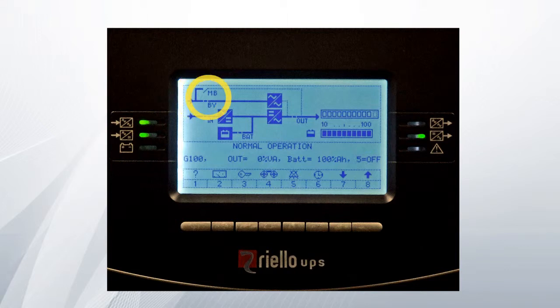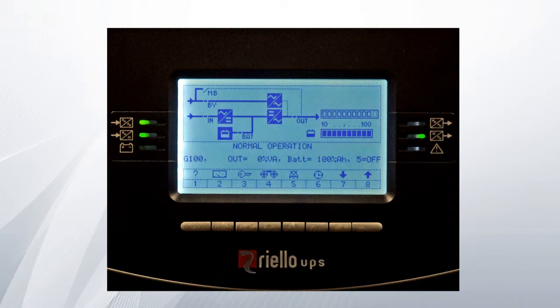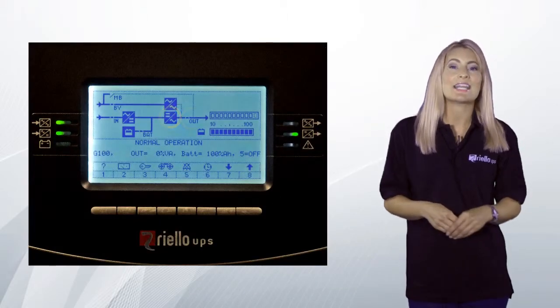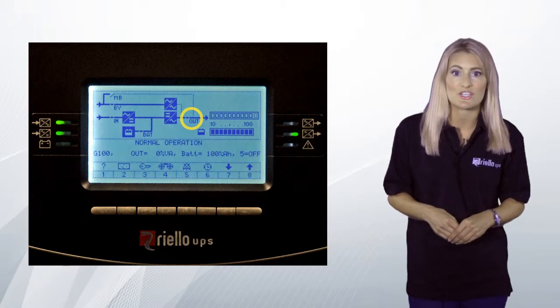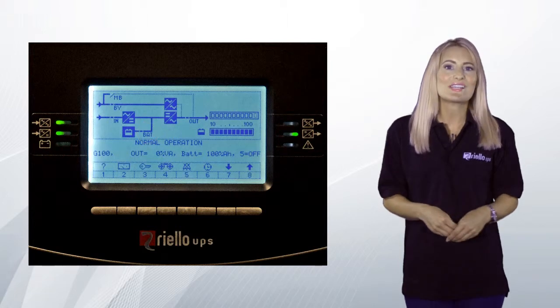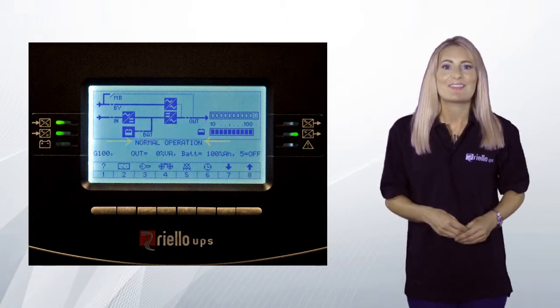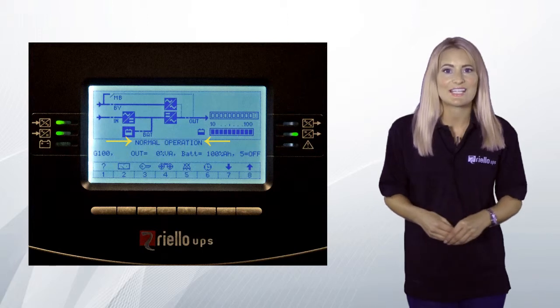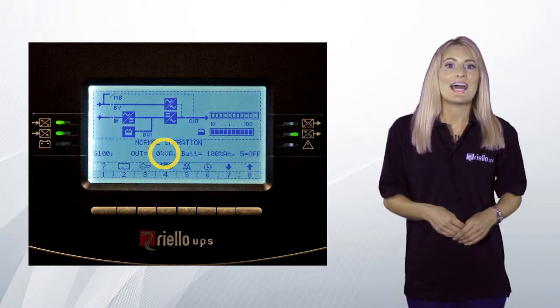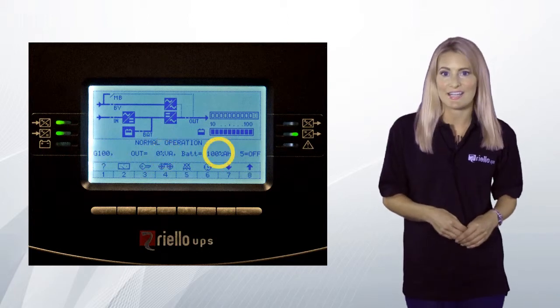The bypass supply switch is closed and the UPS static switch is operational, but not supplying an output. The rectifier input switch is closed and the rectifier is seen to be providing a DC output. The inverter is operating and is providing an AC voltage to the output switch, which is closed. The battery switch is also closed, indicating that the batteries are being charged. The main screen also displays the current operational status of the UPS, as well as the UPS rating, the current applied load and the current charge status of the connected batteries.